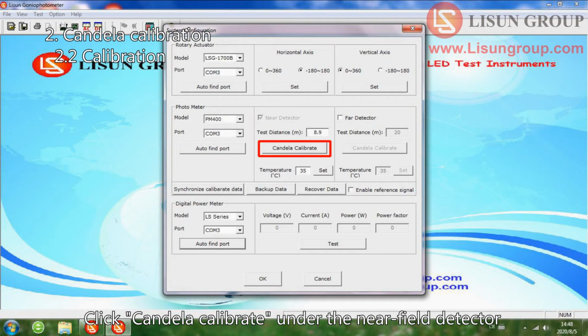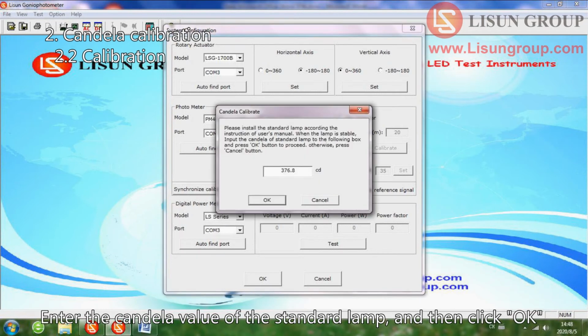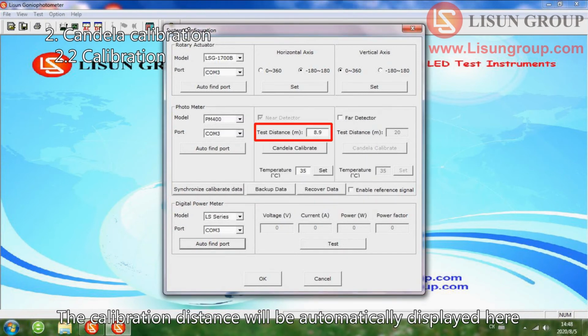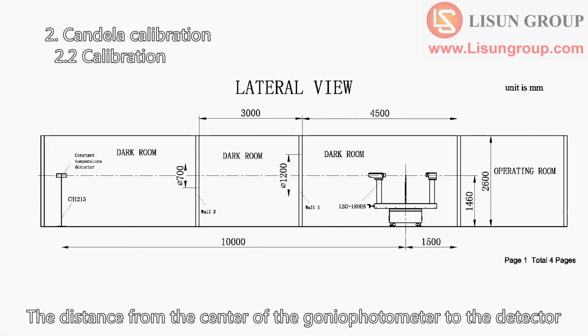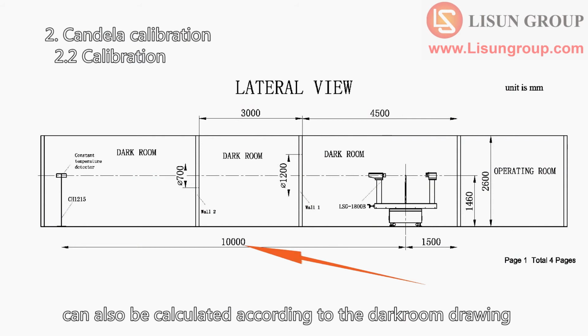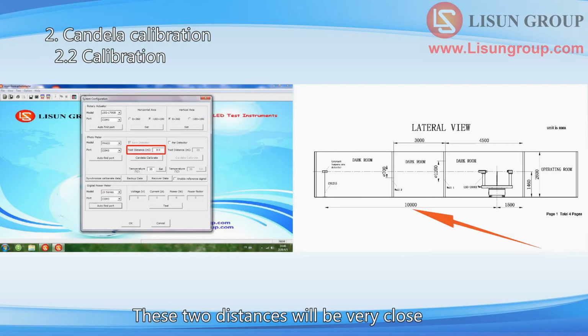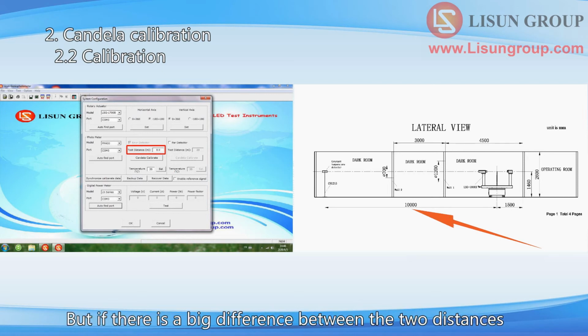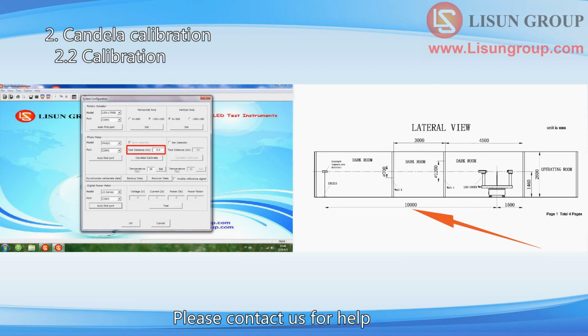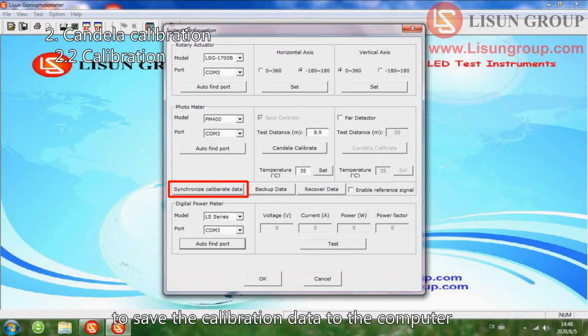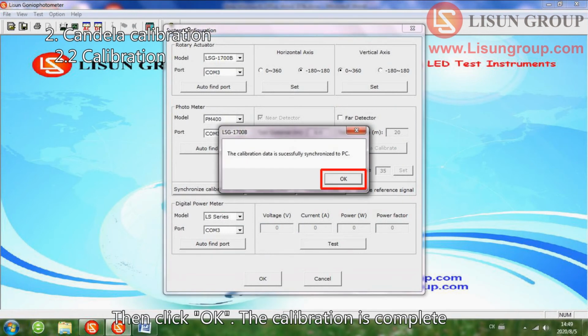Click Candela Calibrate under the near-field detector. Enter the candela value of the standard lamp, and then click OK. The calibration distance will be automatically displayed here. The distance from the center of the goniophotometer to the detector can also be calculated according to the darkroom drawing. These two distances will be very close, but not exactly the same, which is normal. But if there is a big difference between the two distances, please contact us for help. Click Synchronize Calibrate Data to save the calibration data to the computer. Then click OK. The calibration is complete.